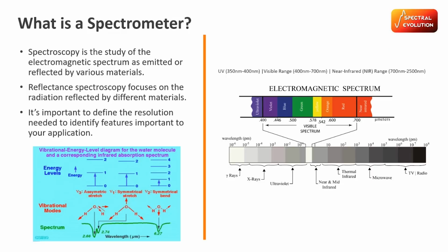So a spectrometer reads the radiation with a radiometric calibration, and it can measure the amount of energy that's coming from something, or the amount of light. For a spectrometer collecting reflectance percent, it will measure a white plate, which is a 99% reflector across the electromagnetic spectrum.